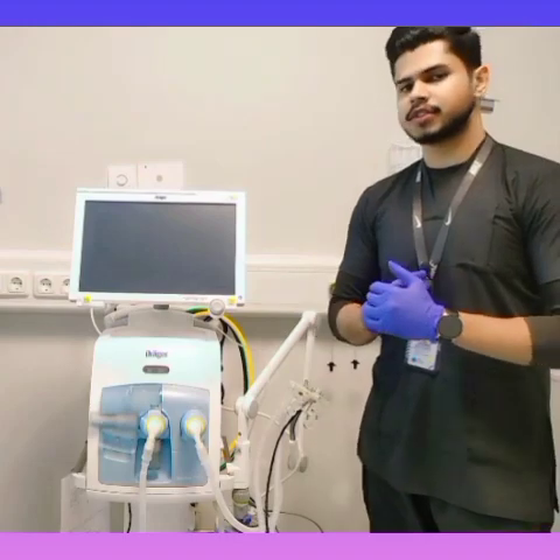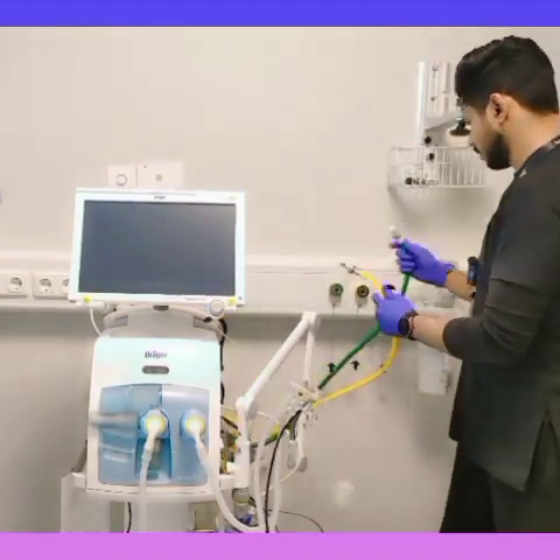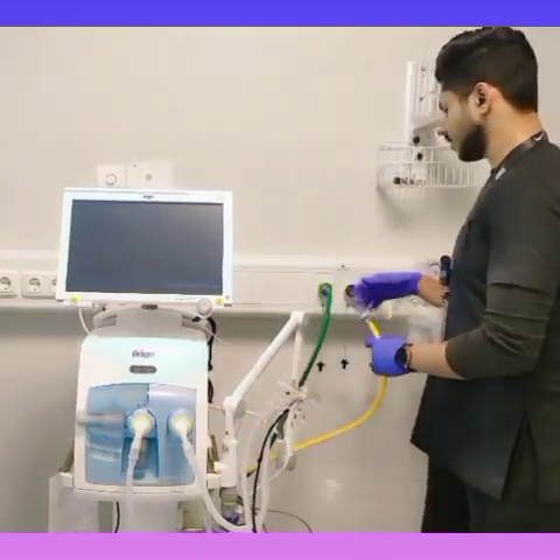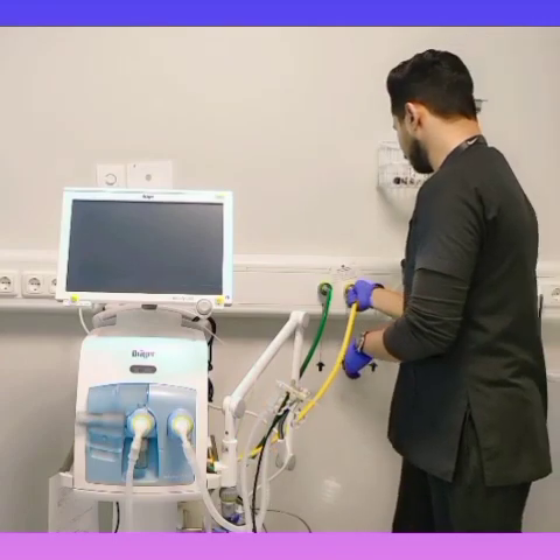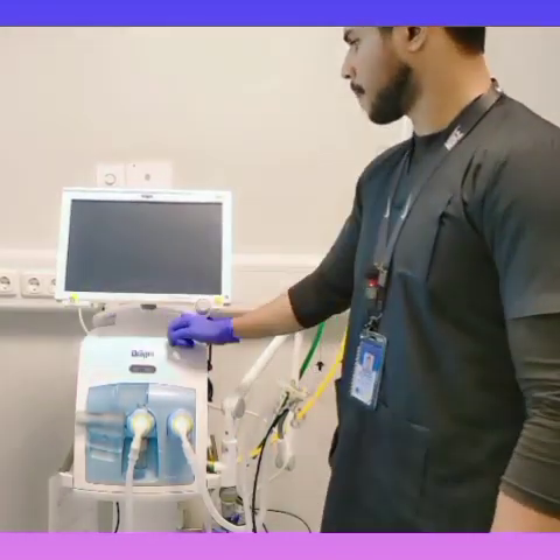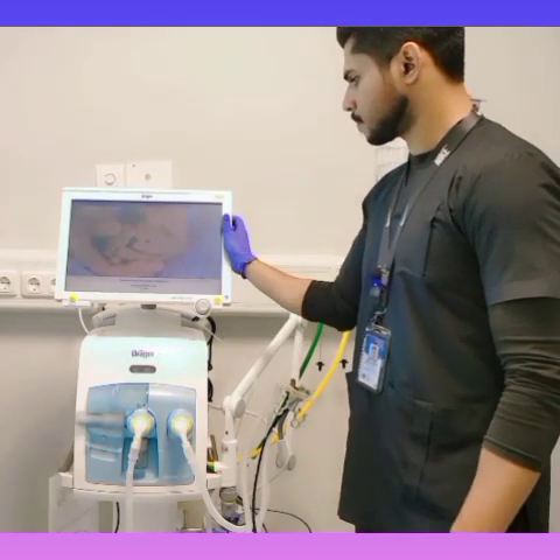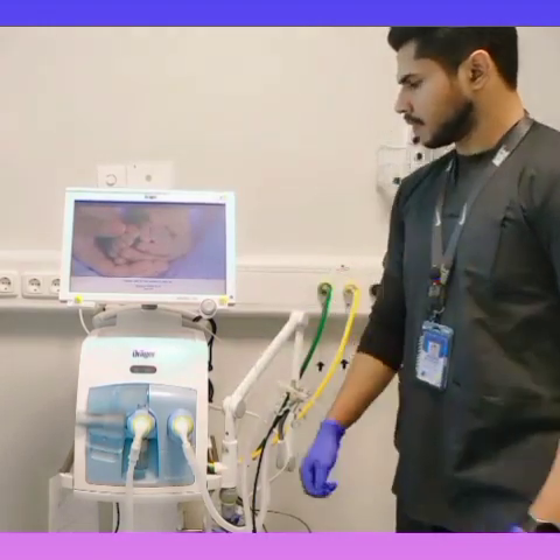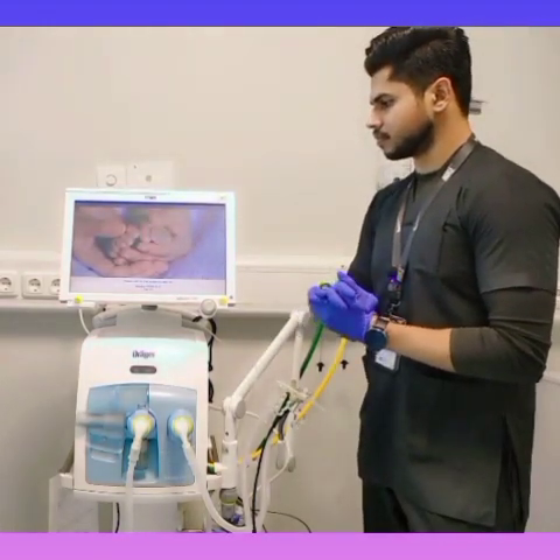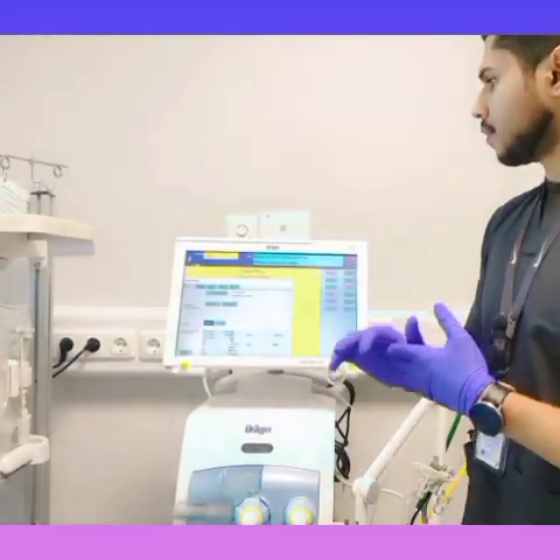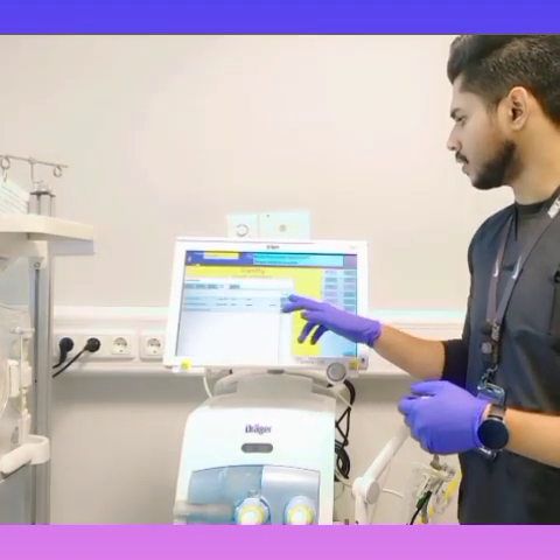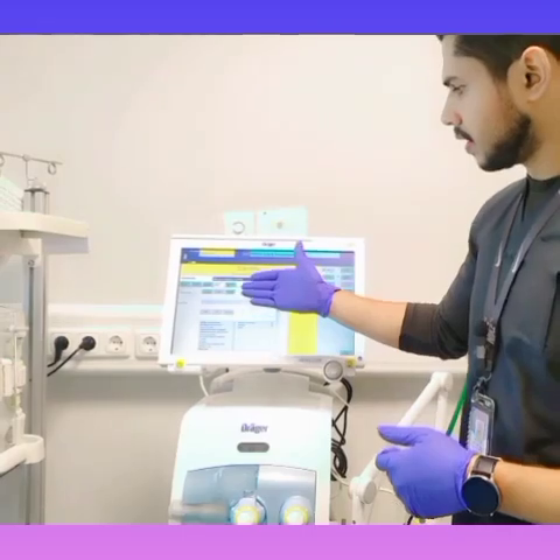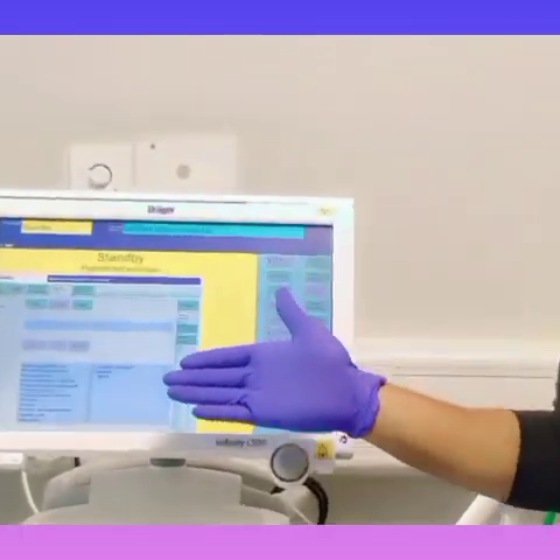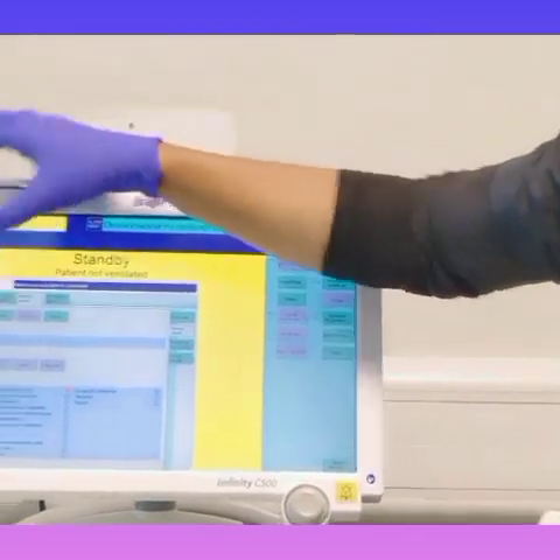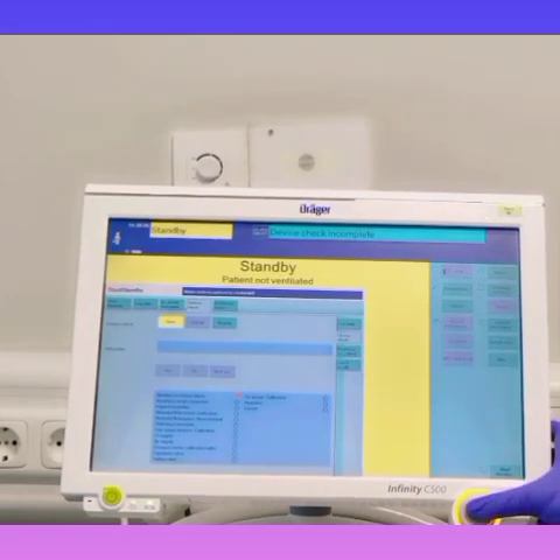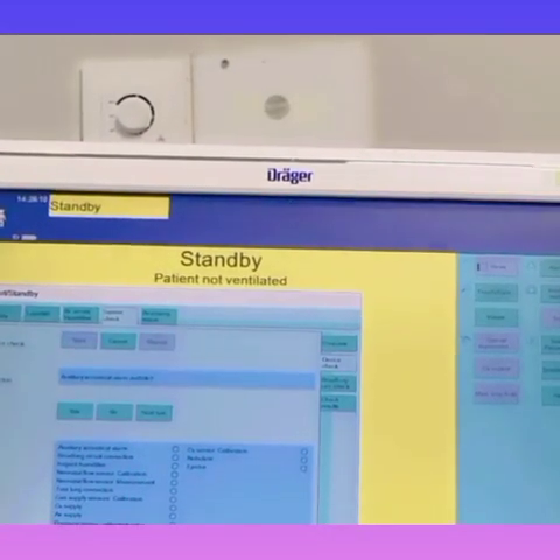The next step is our calibration. This is our oxygen inlet that goes in here, and this is our air inlet that goes in here. So for the calibration, first of all we have to go to the system check, then go to the device check. You can see here there are certain steps you have to follow for the calibration. To start our calibration, we have to press start and then push our rotating knob to start our calibration. Okay.